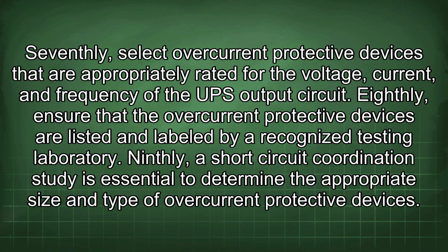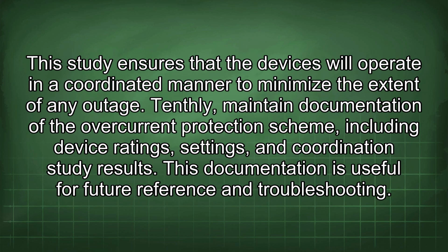Seventhly, select overcurrent protective devices that are appropriately rated for the voltage, current, and frequency of the UPS output circuit. Eighthly, ensure that the overcurrent protective devices are listed and labeled by a recognized testing laboratory. Ninthly, a short-circuit coordination study is essential to determine the appropriate size and type of overcurrent protective devices. This study ensures that the devices will operate in a coordinated manner to minimize the extent of any outage. Tenthly, maintain documentation of the overcurrent protection scheme, including device ratings, settings, and coordination study results. This documentation is useful for future reference and troubleshooting.